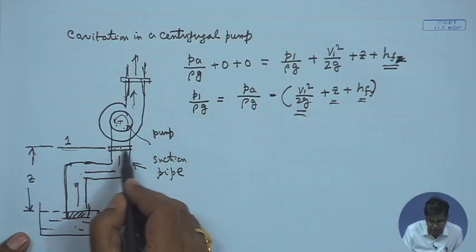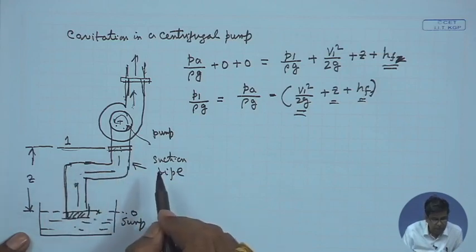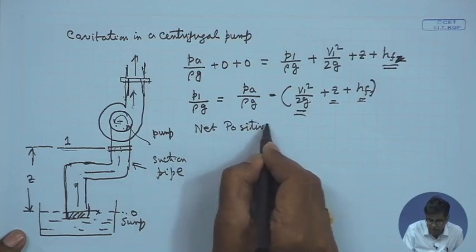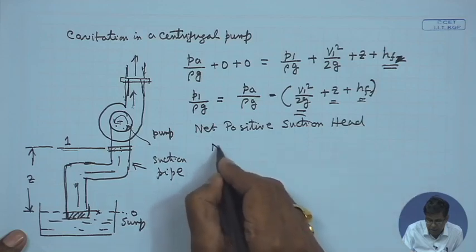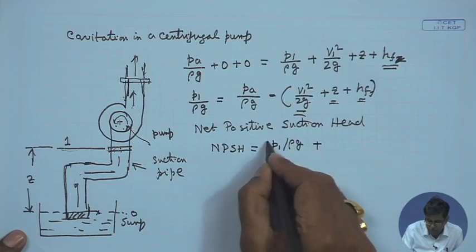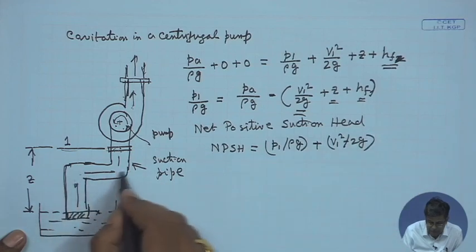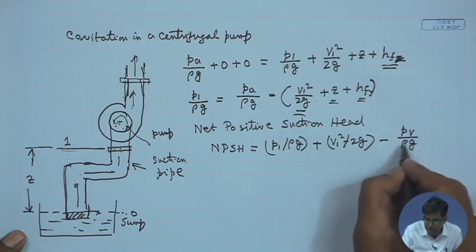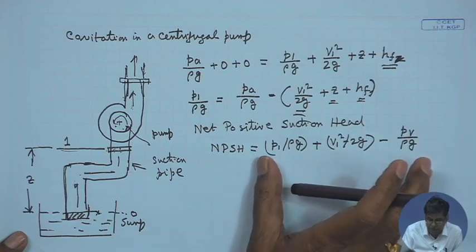There is a likelihood that cavitation may occur here if we allow this pressure to fall below the vapor pressure of the water at the working temperature. We define — in a similar way to turbines — the net positive suction head (NPSH) as the sum of the pressure head plus the velocity head at the outlet of the suction pipe over the vapor pressure head, P_v / ρg, where P_v is the vapor pressure at the working temperature.